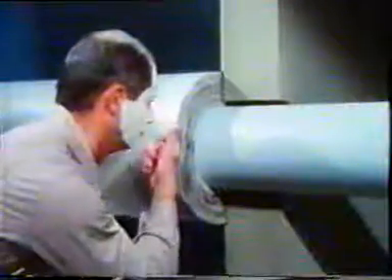But will the seal withstand higher loads? The seal starts leaking due to wear caused by friction. The shaft and housing are far too expensive to be used as wearing parts. Ideally, only the seal faces should be changed.